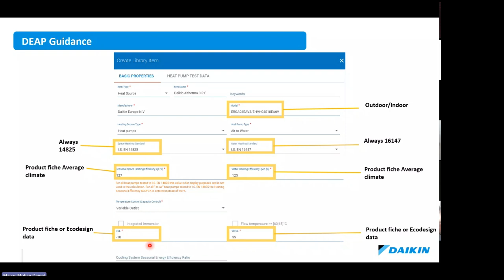Now, if we take a look into one of the heat pumps to add it into DEAP, basically you create a new library item, you add it in as a heat source, an air to water heat pump, and you put in your model, make, and the heating and water standards. So this is always going to be EN14825, EN16147. And then these are your efficiencies from the ecodesign data. And then these are your temperature operating limits.